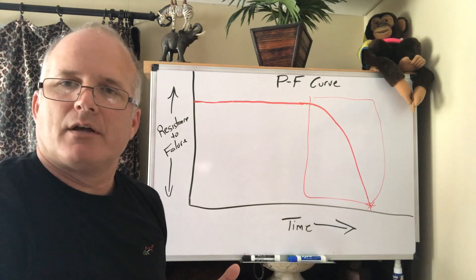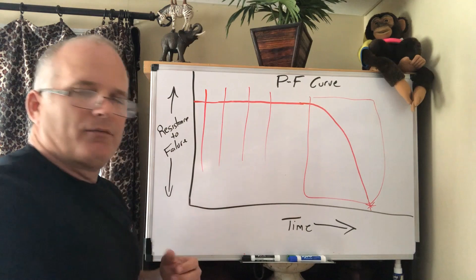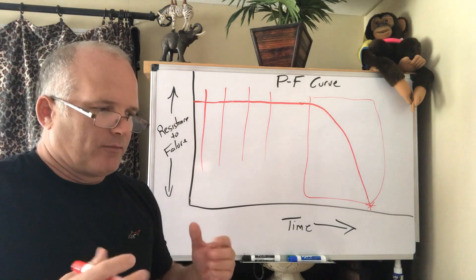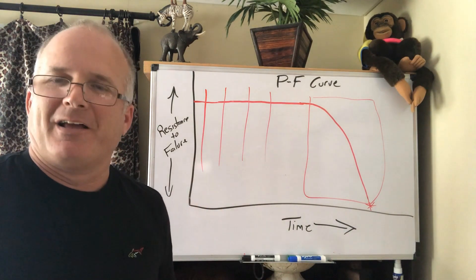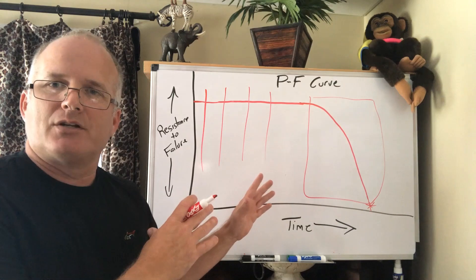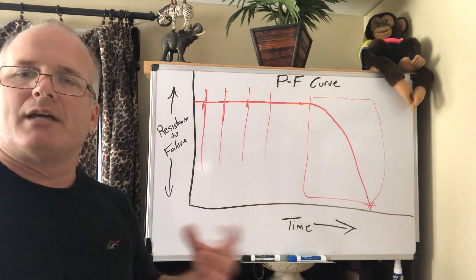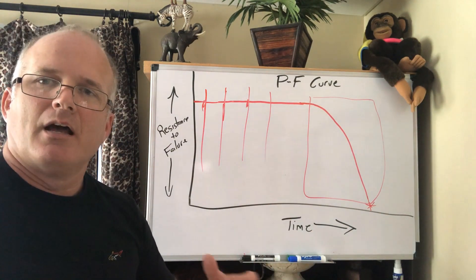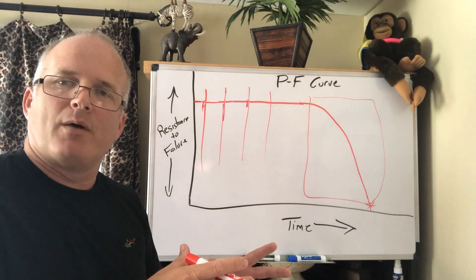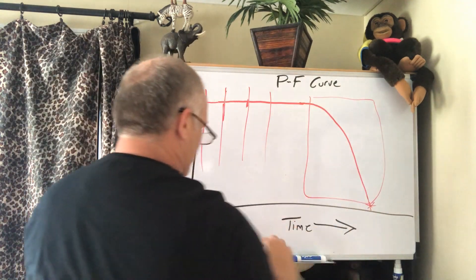Most organizations, even top-tier ones, have inspections where they look at equipment periodically. But if you're talking about a pump and a bearing, what do you actually look at? From a time-based maintenance perspective, it's just whether it's rotating. The best approach is applying technology at some interval — looking at the health of that bearing with vibration analysis, ultrasonics, or oil analysis — where you can really see what's happening inside that piece of equipment, just like going to the doctor where they extract blood from you.